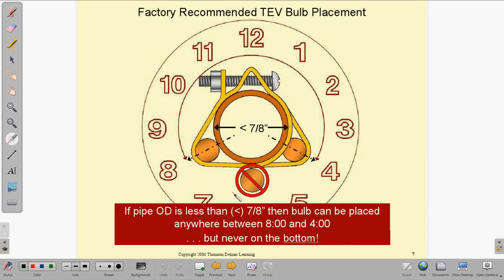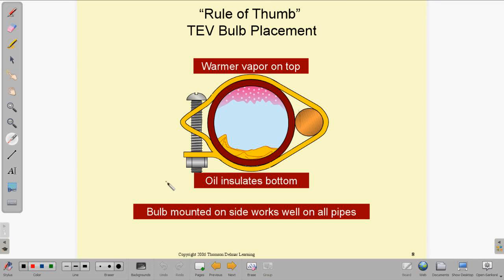Now, if the outside diameter is less than 7/8 inch, then the bulb can be placed anywhere between 4 and 8 o'clock here. Now, you never want to place it at the bottom, and it's a pretty good idea just to keep it right here at the 9 and 3 if you can. It's just not always possible to do that. The reason being is the TXV sensing bulb senses the temperature, and if it's right up here at the top, it's a little bit warmer at the top of the tubing because the vapor rises to the top, and it's going to throw the sensing bulb off a bit.